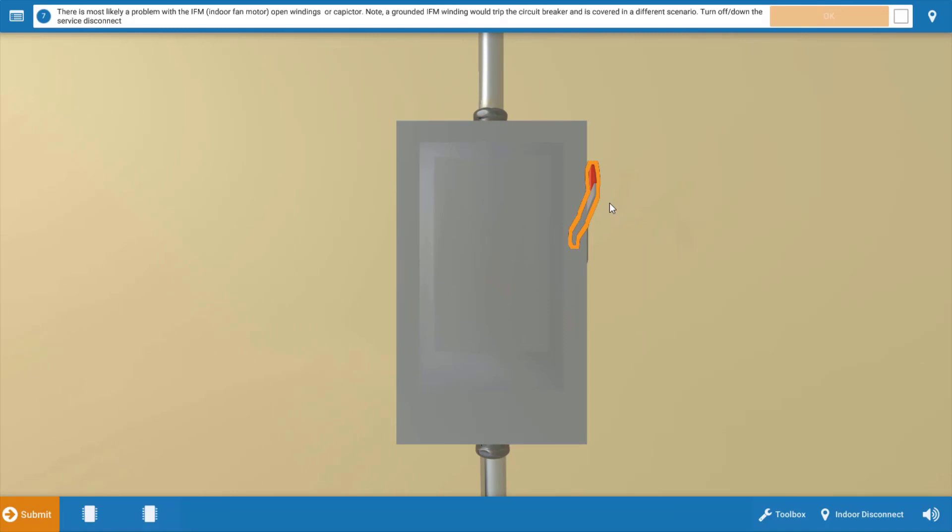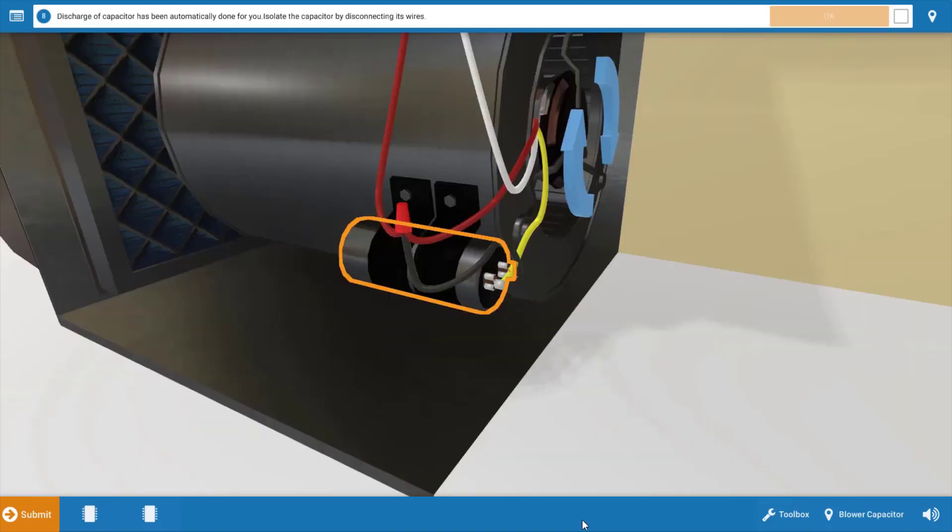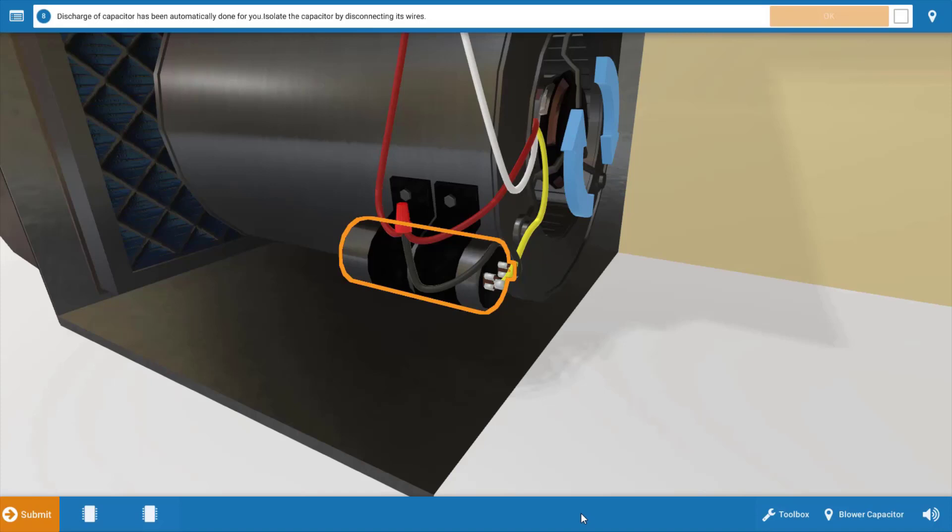Our next step is to turn the power off. We're going to have to measure resistance and capacitance here, and we can't do that with the power on. Now our next step is to discharge the capacitor. This is an important safety consideration. Always be sure to discharge a capacitor prior to disconnecting the wires from it. This has already been done for us in the simulator.